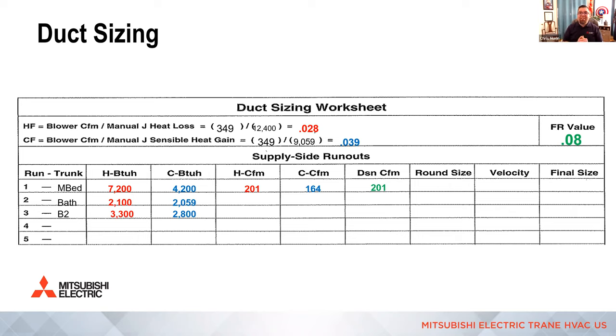Everybody good so far? So a question came in. Why are we ignoring latent dehumidification? We're not ignoring it. We're handling it at the coil. That's why we have return ducts. We need to remove the moisture at the coil. The latent demand in the space is still there, but if we don't get the air back, we can't remove the moisture because it doesn't come across that cold coil. Only sensible temperature is changed when it comes to airflow. So airflow is actually going to change the sensible temperature, the number you see on the thermostat, right? All the dehumidification is taken out when the air gets back across that cold coil.